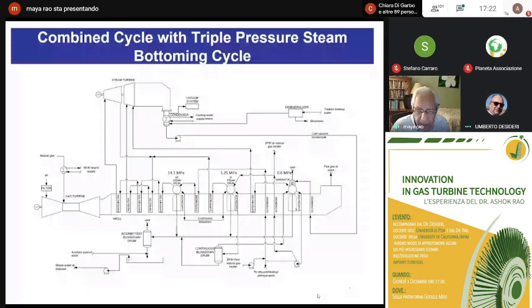Now this shows a full-blown modern combined cycle, a large-scale combined cycle, with 3 levels of steam pressure. You have multiple pressures because you want to minimize the irreversibility in the heat exchange in the gas turbine exhaust, and maximize the amount of heat recovery from the gas turbine exhaust. I won't go through the details of this diagram.